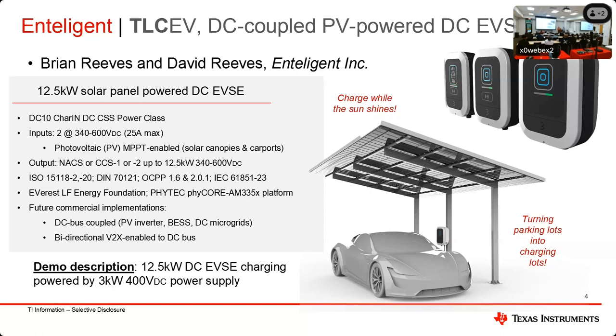How would you feed the car through the microgrid? You would have to convert from DC to AC, so you have to have an inverter. Say you want to hook up a level 2 AC charger. That charger would then pump the car 240 volt, 40 amp AC. Then the car needs to convert that AC back to DC. That round trip, you lose about 25%.